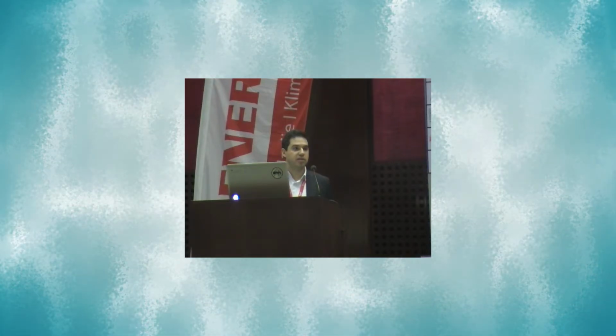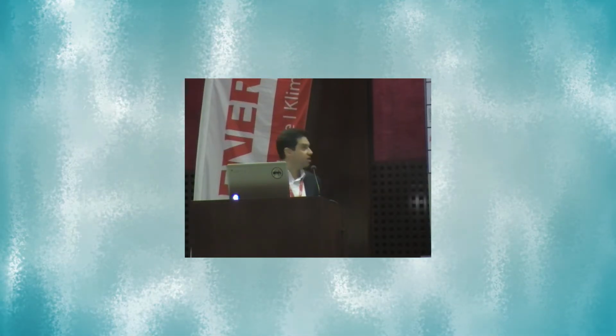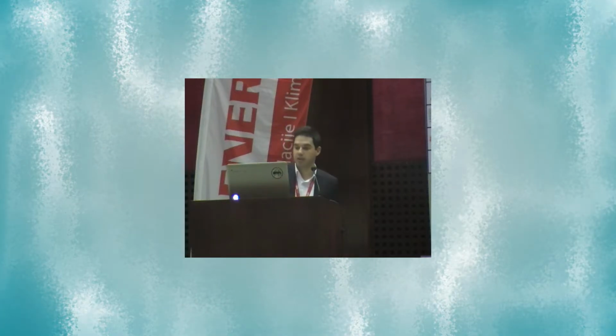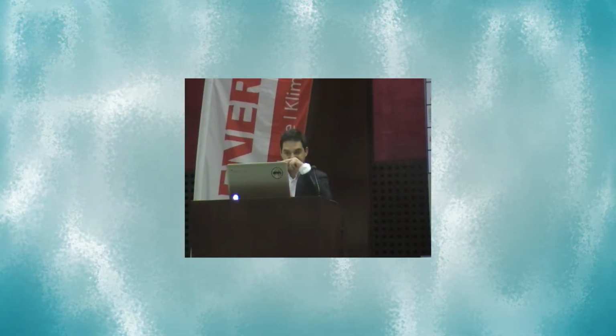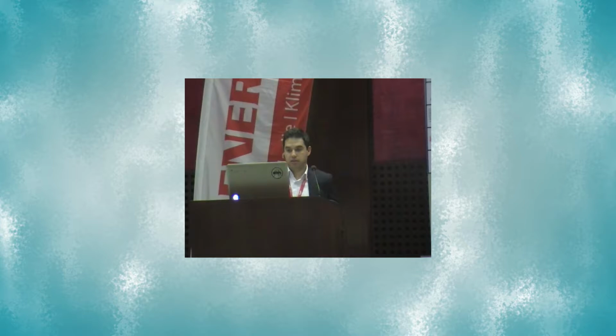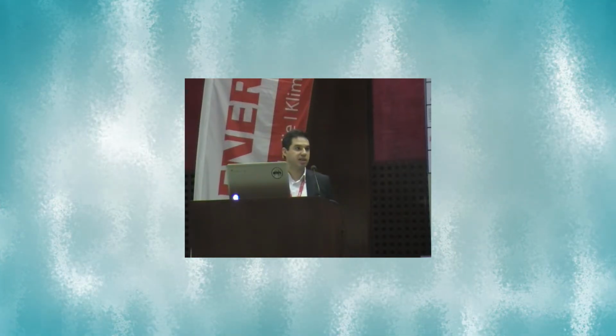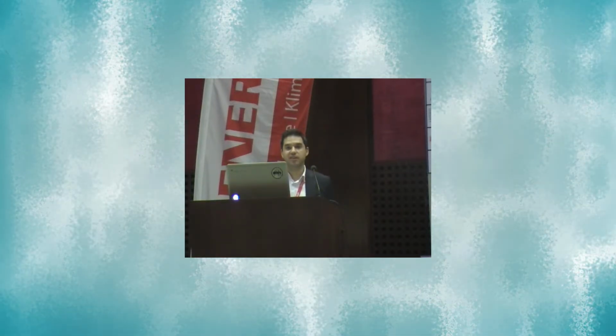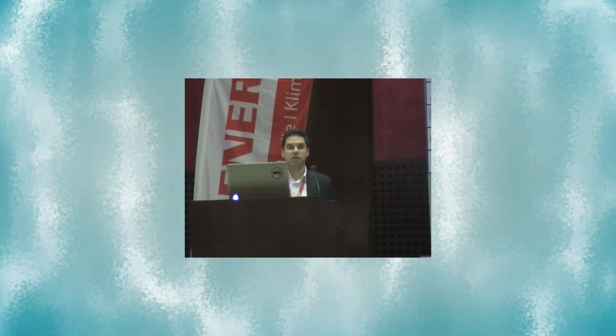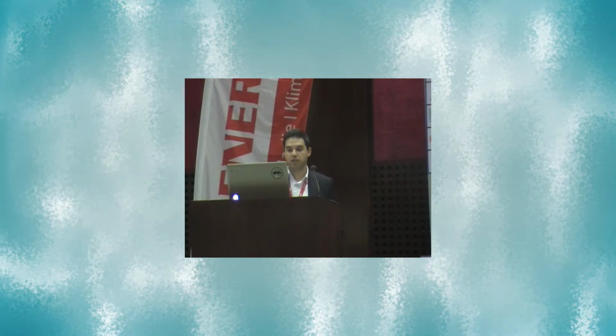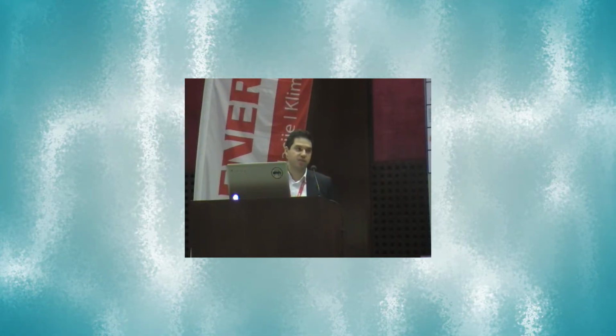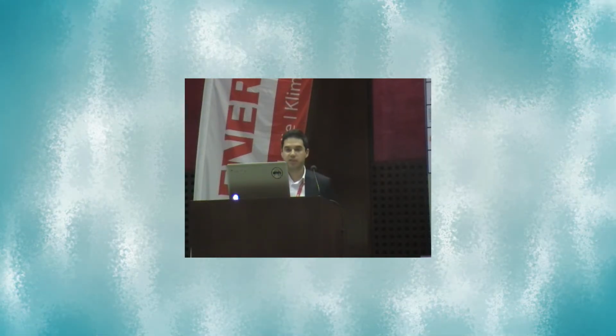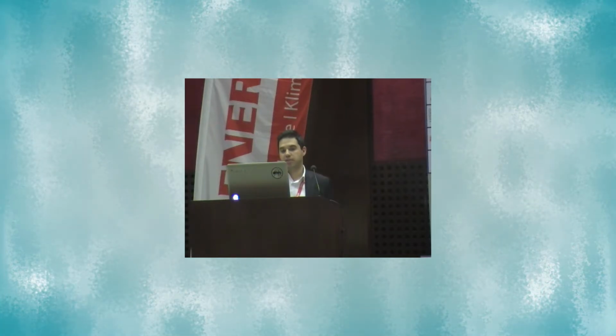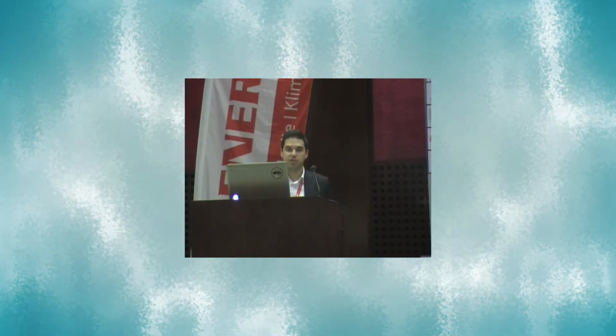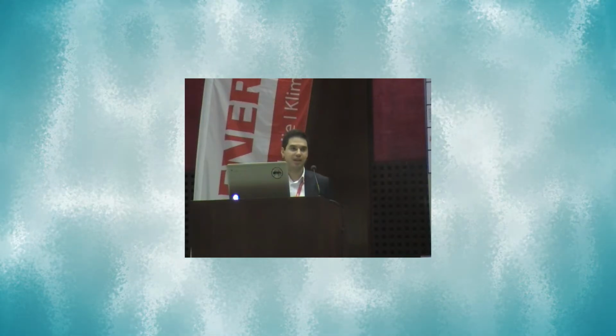Another thing where we can save a lot of energy are the display cabinets. Here on the picture is the open multi-deck cabinet, and there are some studies. If we introduce glass lids or glass doors, we can save at least 40% energy. You can see on the photo, 75% of the energy consumed comes from the air infiltration, 5% thermal conduction, heat radiation, and 5% through fans and lighting.